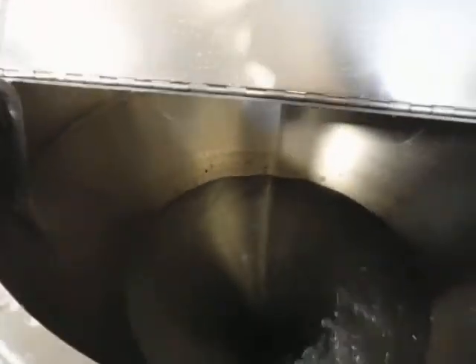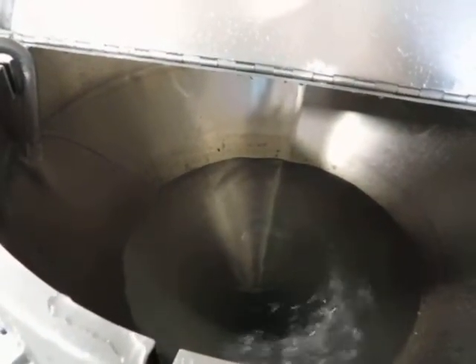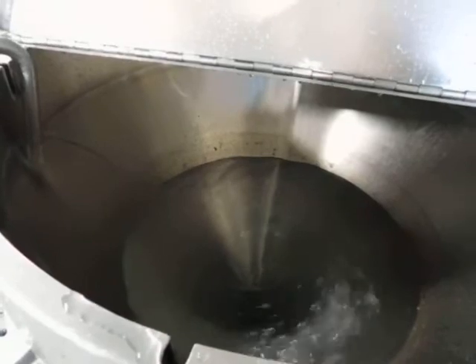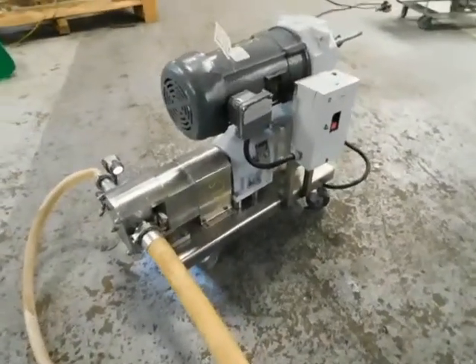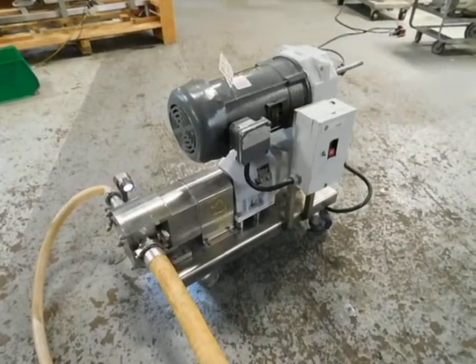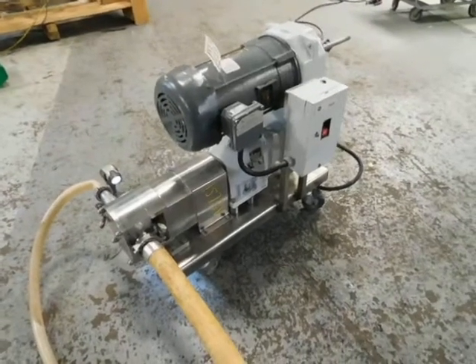Looks like we're running — we'll call that 20 to 25 GPM. We have tested the variable speed on the pump; controls are usable. We're operating on 220V, 3-phase voltage right now.